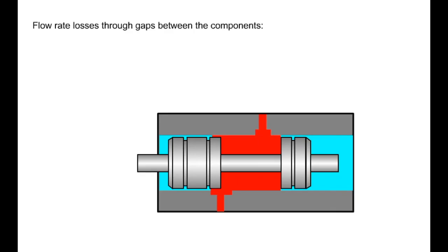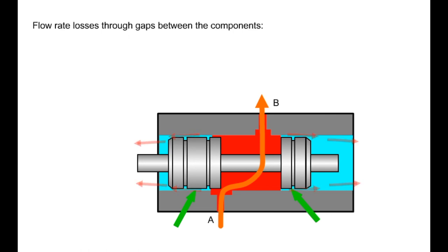Volumetric efficiency is based on loss of usable pressure fluid — meaning that part of the flow rate supplied by the hydraulic pump is lost. This happens everywhere where there are gaps between components through which pressure fluid can escape, for example between movable parts. In a directional control valve, a small portion of pressure fluid is pushed through the clearance gap required for the spool to move within the housing. Other flow rate losses occur at gaps allowing fluid to flow for lubrication or cooling purposes. The leakage pressure fluid is often fed back into the hydraulic circuit through a separate leakage line.